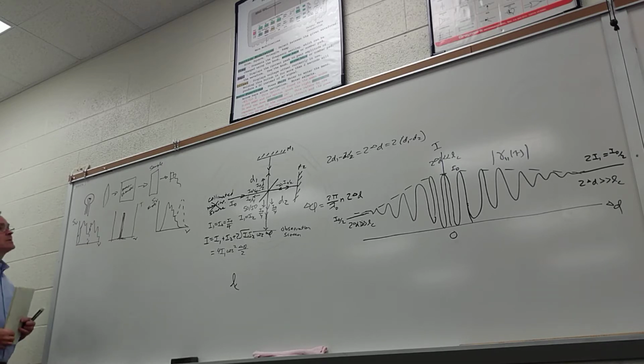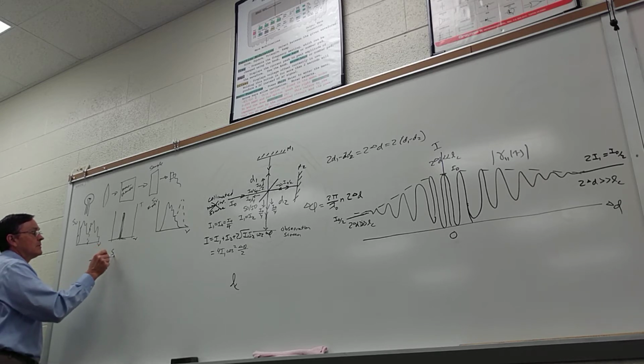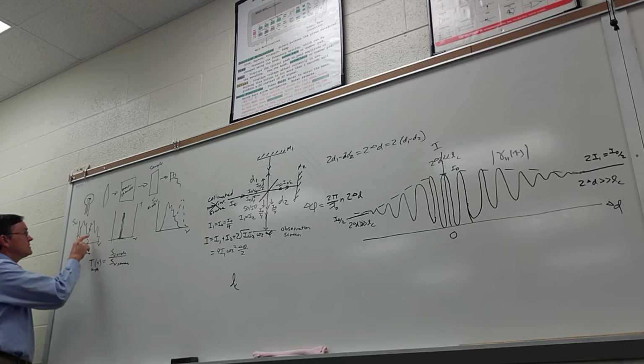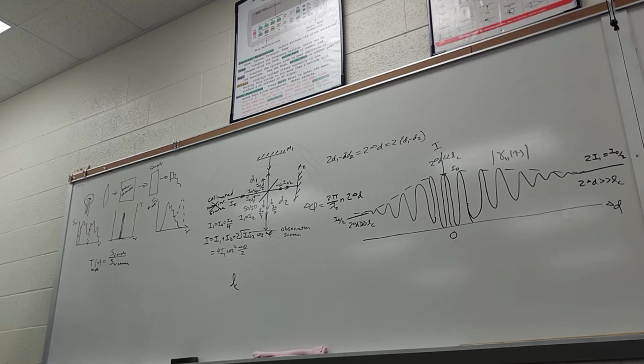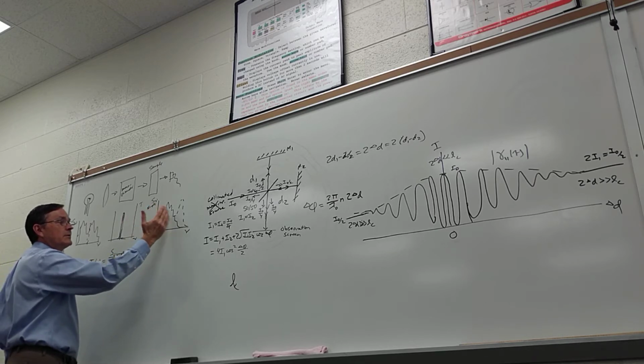Okay. So what we want to know is the transmission as a function of, let's say, frequency or wavelength, of our sample. Well, it's just going to be the power spectrum of the whole system with the sample in it divided by the power spectrum of the source. Before the monochromator. The monochromator, all it does is allow us to make this measurement wavelength by wavelength.